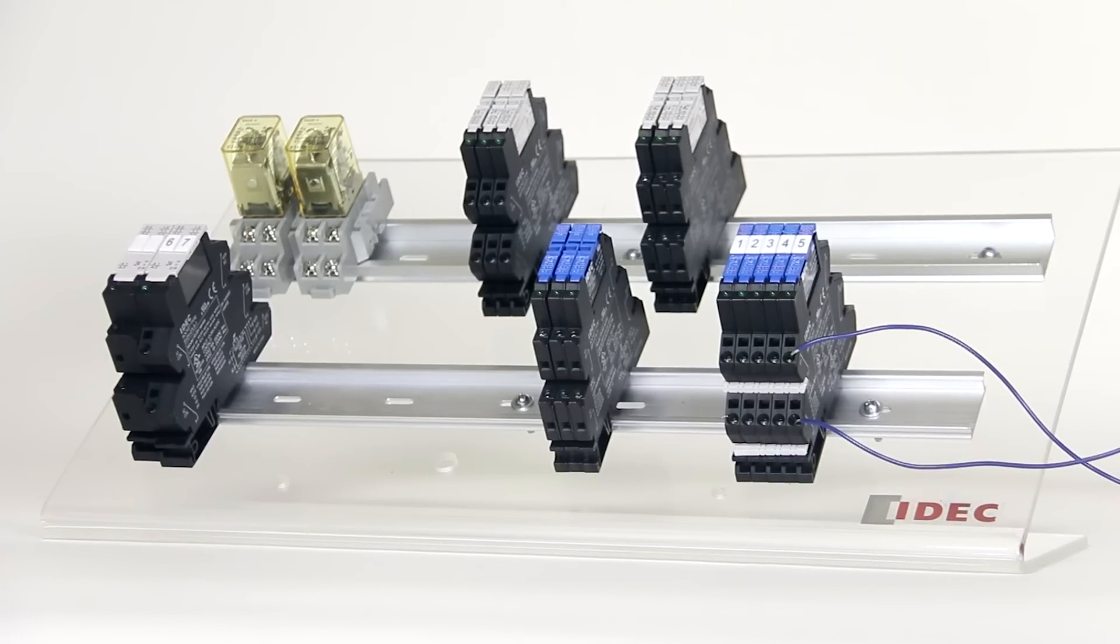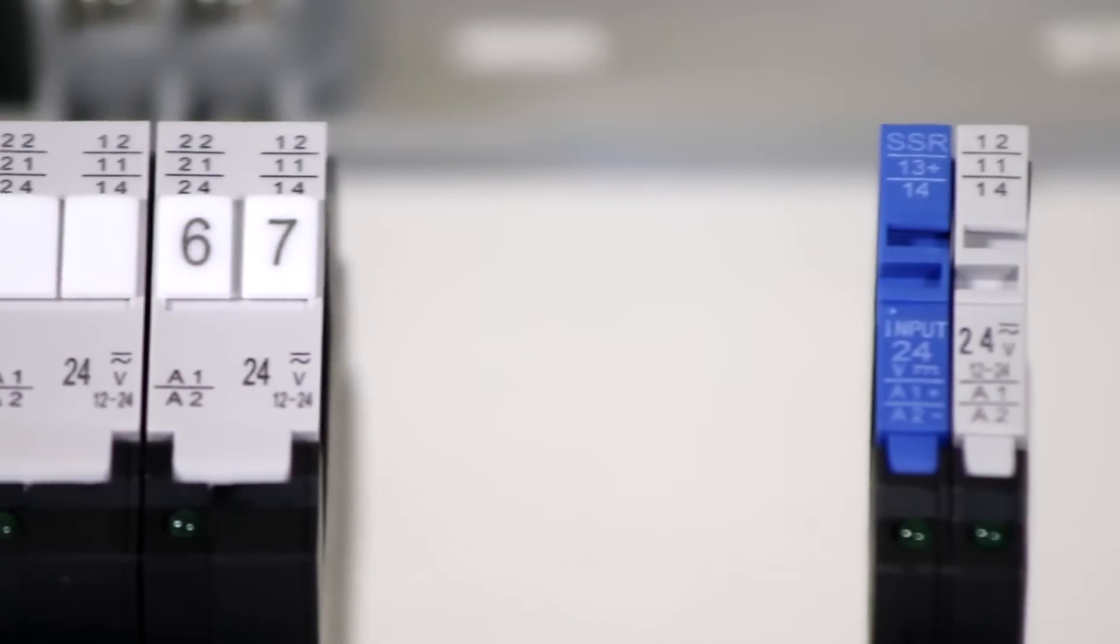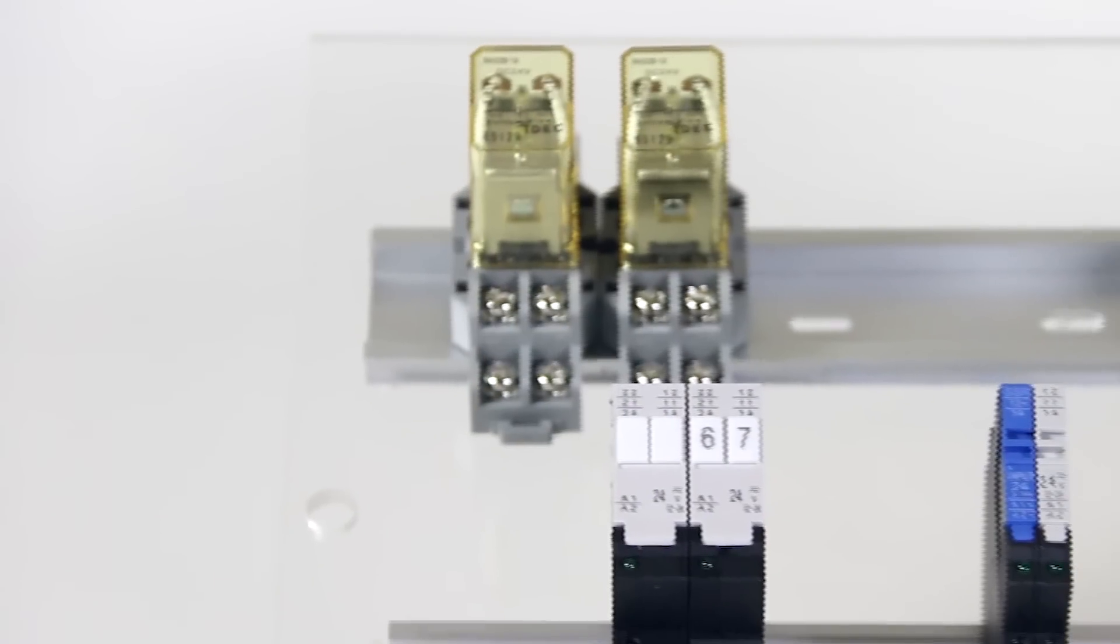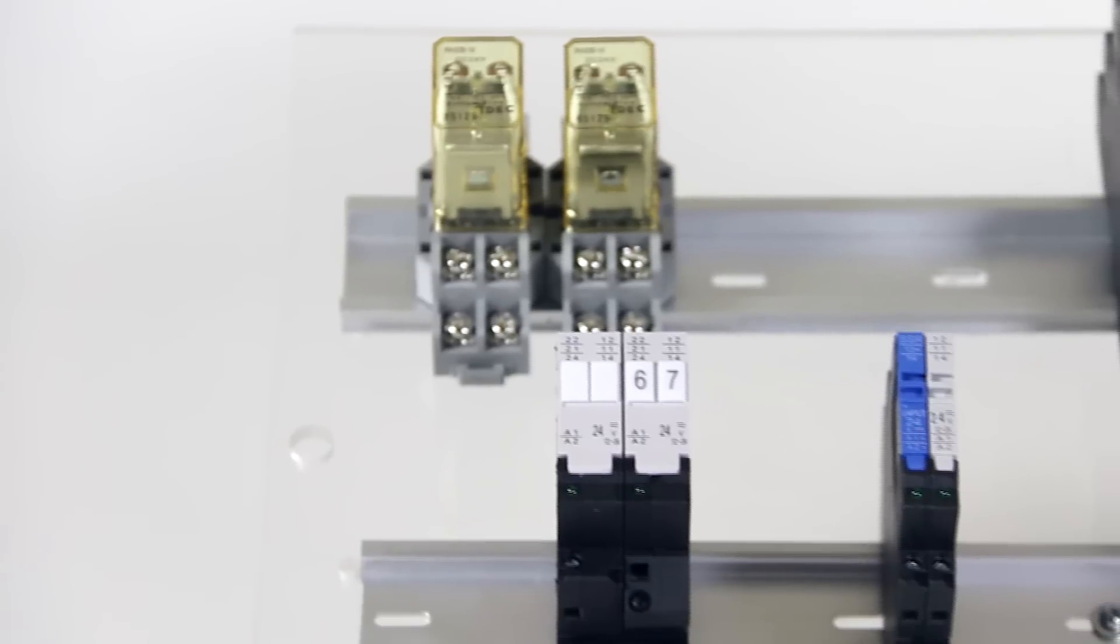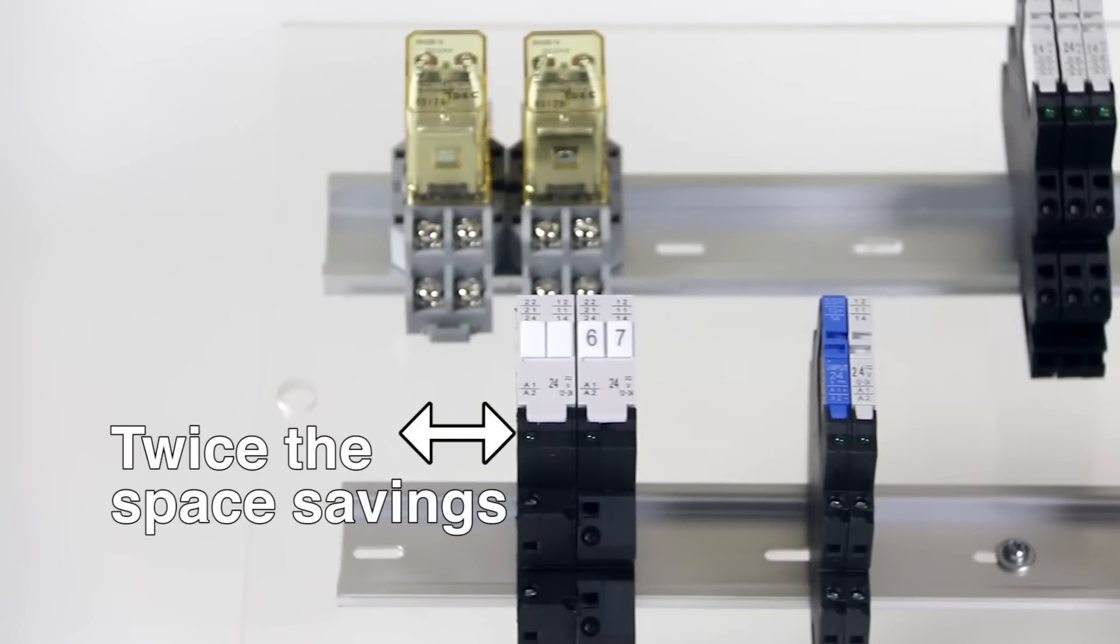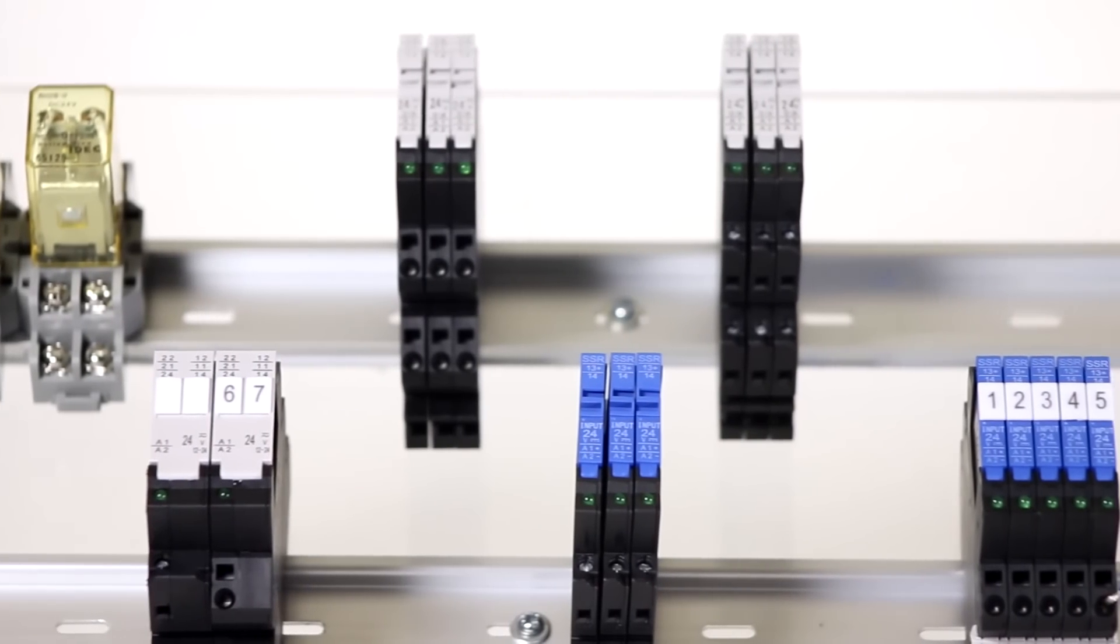These new relays are much more compact than prior versions with similar functionality. Compared to our RH2 ice cube relays, the 14 millimeter versions of the RV8 take up only half as much space, allowing you to install twice as many relays along the length of DIN rail.